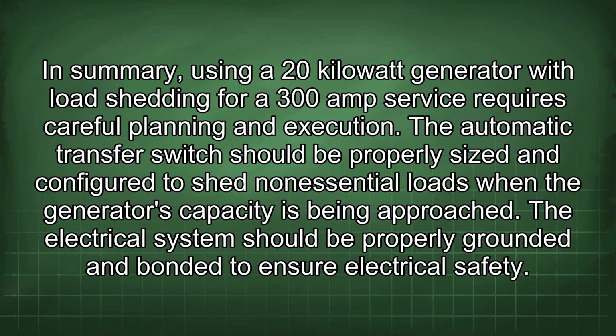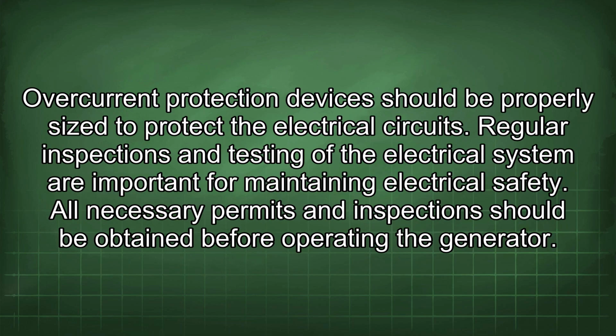In summary, using a 20 kilowatt generator with load shedding for a 300 amp service requires careful planning and execution. The automatic transfer switch should be properly sized and configured to shed non-essential loads when the generator's capacity is being approached. The electrical system should be properly grounded and bonded to ensure electrical safety. Overcurrent protection devices should be properly sized to protect the electrical circuits. Regular inspections and testing of the electrical system are important for maintaining electrical safety. All necessary permits and inspections should be obtained before operating the generator.